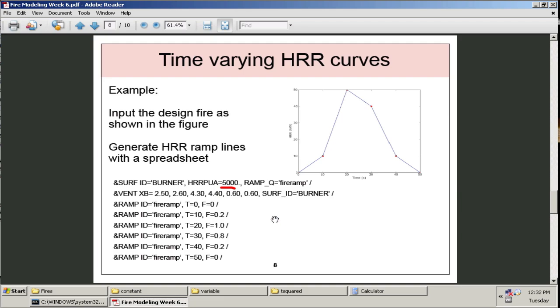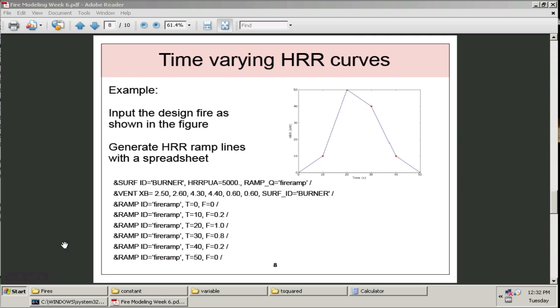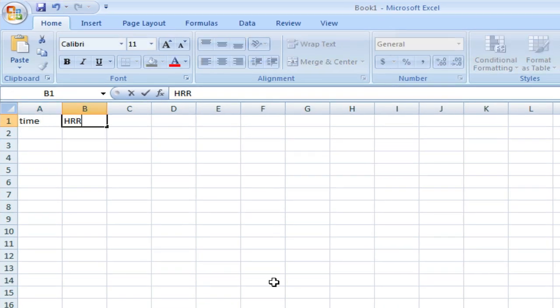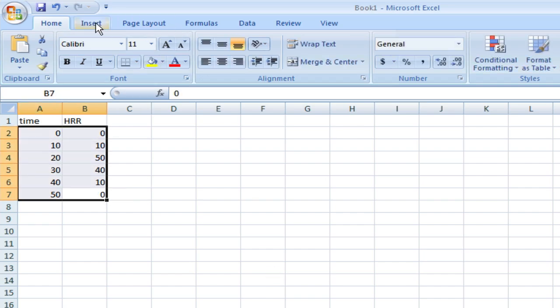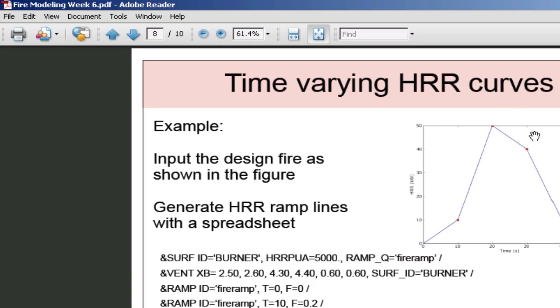If I open up Excel, I'll show you how you can generate these fraction values fairly easily. And we'll put them into the room fire case. So, if I open up Excel, the first thing I want to do is have a column for the time and heat release rate, and this represents my input design fire. So, if I have times 0, 10, 20, 30, 40, and 50, and the corresponding heat release rates I've chosen are 0, 10, 50, 40, 10, and 0. If I make a simple plot of this heat release rate design curve, I'll see something similar to the design curve that was on the slide here.